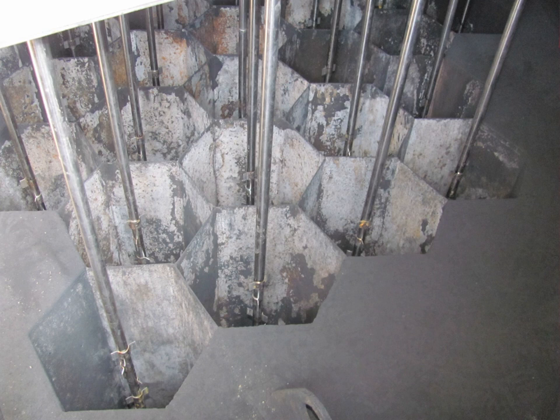Topic: high resistivity. If the voltage drop across the dust layer becomes too high, several adverse effects can occur. First, the high voltage drop reduces the voltage difference between the discharge electrode and collection electrode, and thereby reduces the electrostatic field strength used to drive the gas ion charged particles over to the collected dust layer. As the dust layer builds up, and the electrical charges accumulate on the surface of the dust layer, the voltage difference between the discharge and collection electrodes decreases. The migration velocities of small particles are especially affected by the reduced electric field strength.